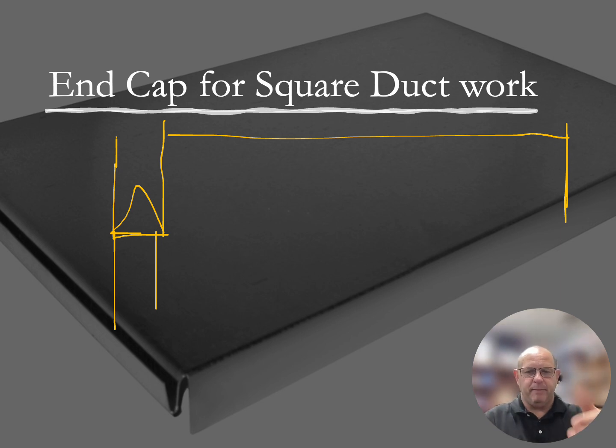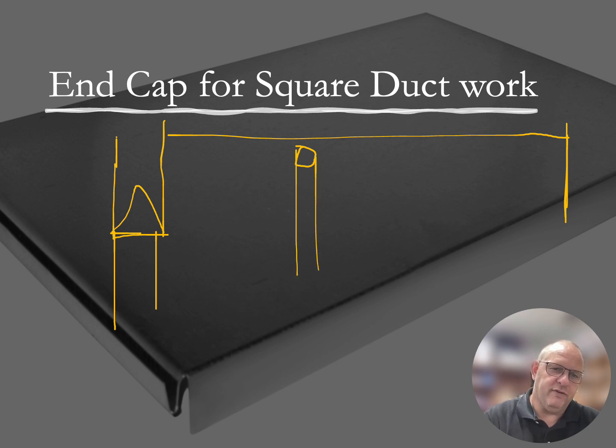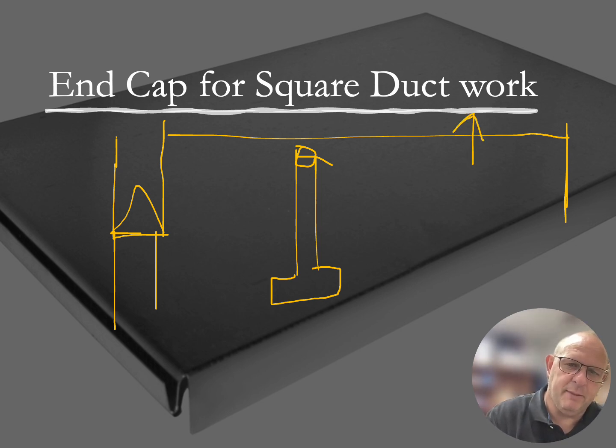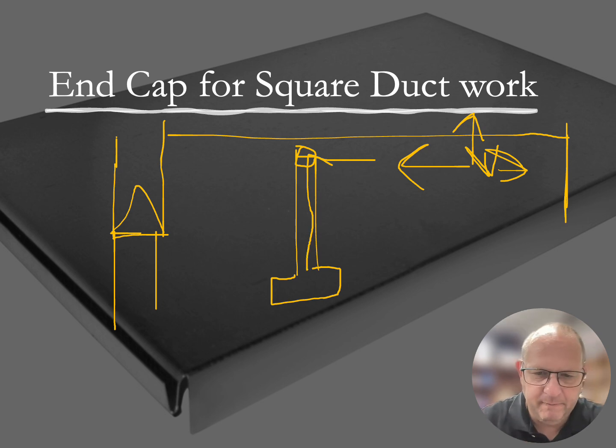What this is going to do for us is back that airflow up, create that static pressure, create that total pressure that we need within the system to push that air out. The different types of trunks are running along this entire system. So branch trunks would run off of there over into a boot type system. And don't forget about our dampers that are in that trunk as well. So this end cap is going to create that pressure that's going to force that air up, down, forward, and also backwards as we create that pressure. So air pressure in all different directions. And as it builds back, it's going to force that air evenly throughout all the branch runs that are in this particular system itself.